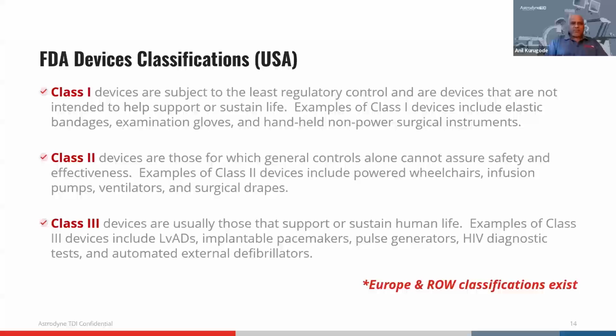Because the FDA actually governs these 3 classes as we discussed before, and in addition to the other configurations like equipment earth, the BF, CF, B category, there's the FDA classification, which requires certain types of rigor to be built into the design. This requires a little more detailed assessment. But just be aware that the FDA is always involved when medical products are being designed and certified. It's one of the long poles in the tent. And companies in this business are keenly aware of how much control is enforced by the FDA.